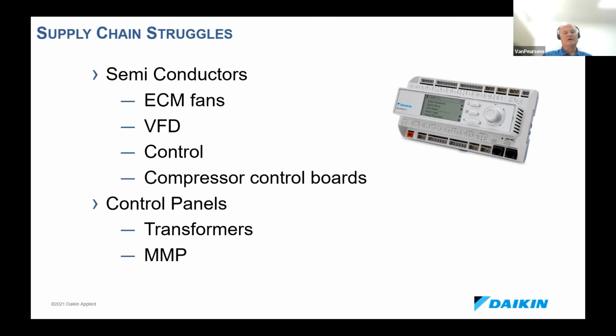Some of these components are factory installed, like on a package rooftop unit. Other components, on product lines such as indoor air handlers, the VFD can be part of the electrician's specification. Instead of operating under just-in-time with VFD supply chain issues, if it's under the electrical spec, they can plan well in advance for field-installing those VFDs if there's an issue getting them.